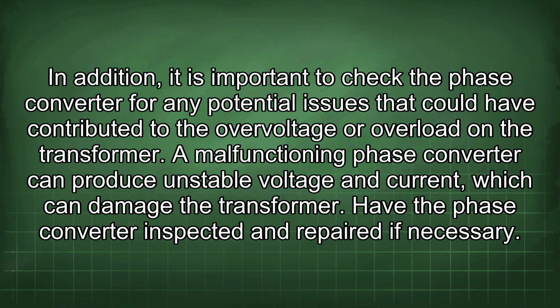In addition, it is important to check the phase converter for any potential issues that could have contributed to the overvoltage or overload on the transformer. A malfunctioning phase converter can produce unstable voltage and current, which can damage the transformer. Have the phase converter inspected and repaired if necessary.